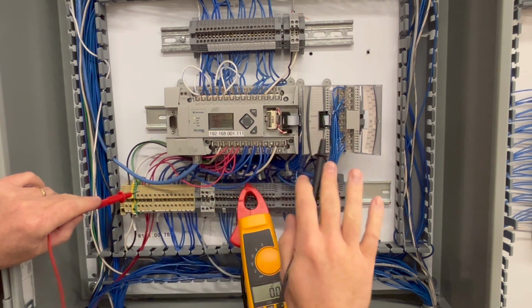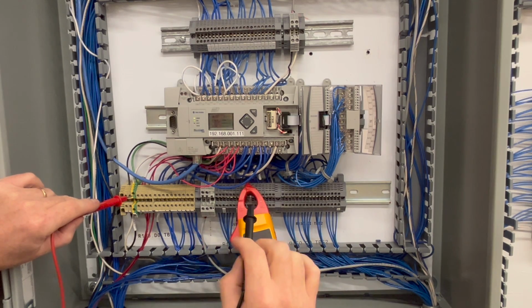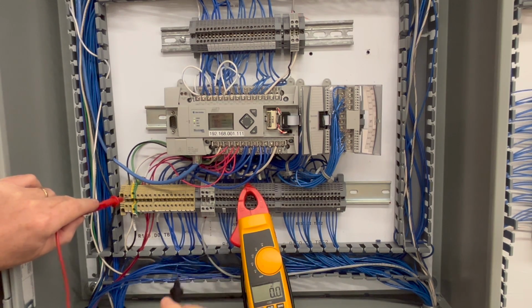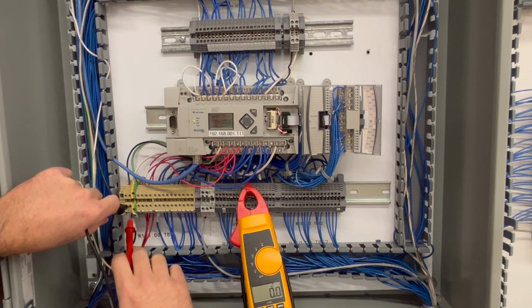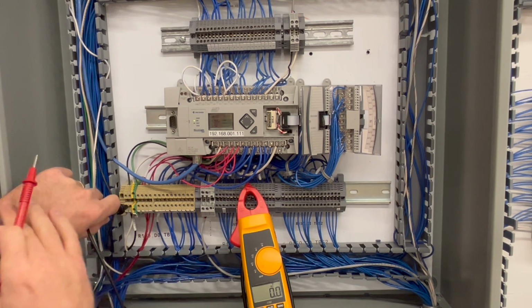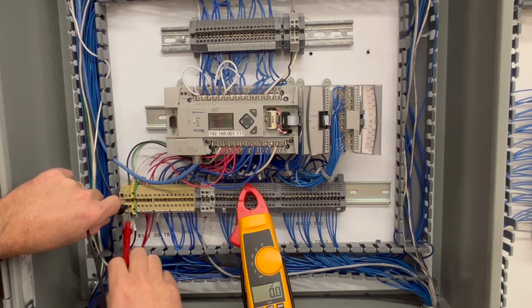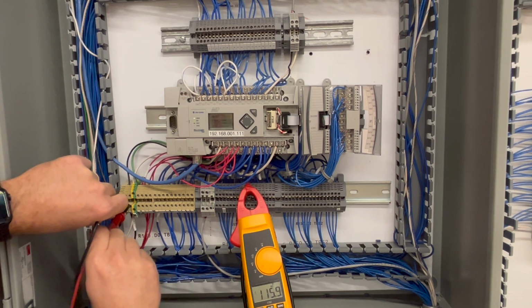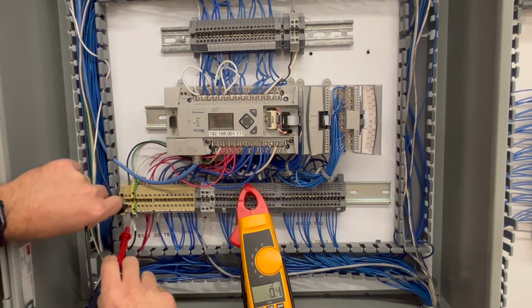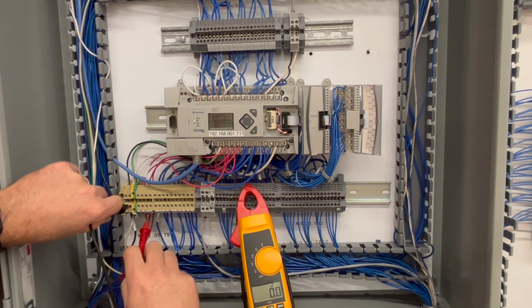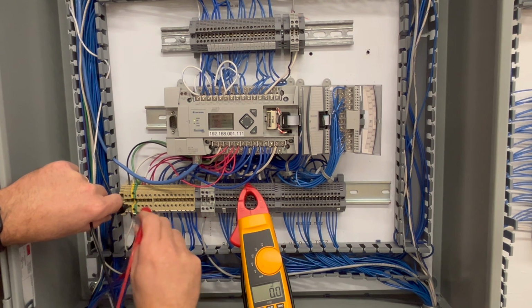Now, this is where things get different. Every PLC will be a little bit different. But when you're checking an output, you want to put your neutral in a place where you know that it has a signal. So we went ahead, verified this is 120, so I'll leave my neutral here. So I'll come in here and I'll test the terminal block at 1.